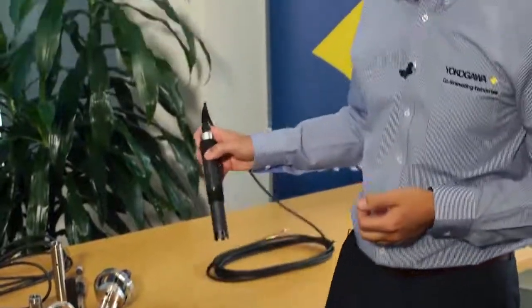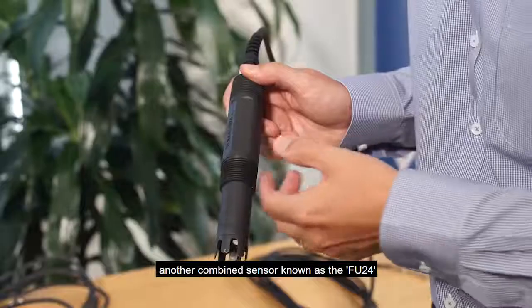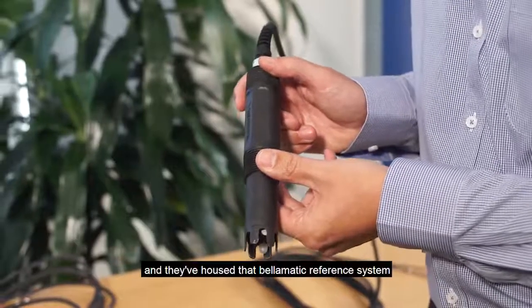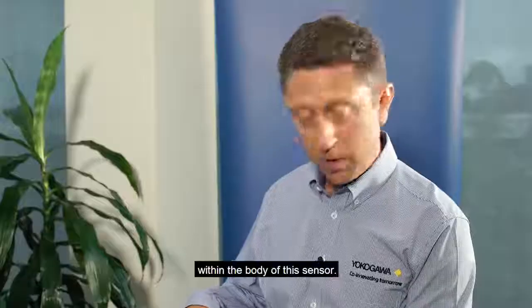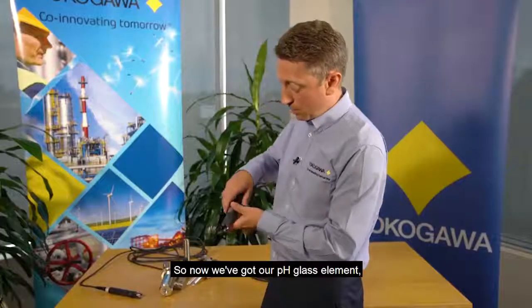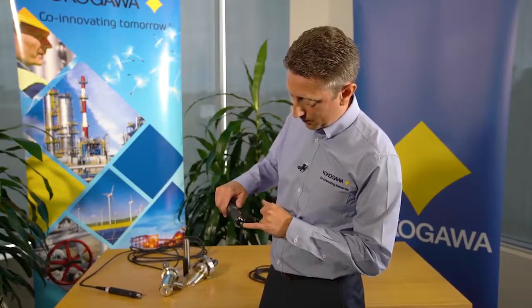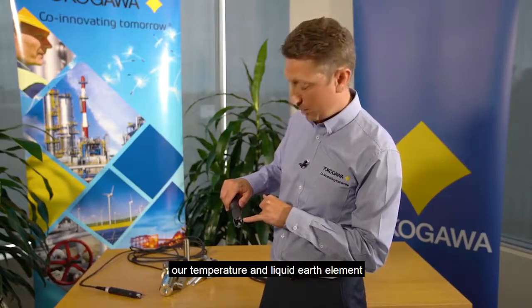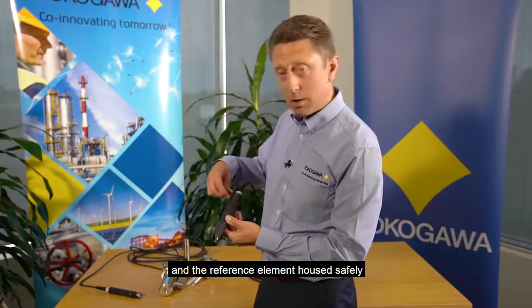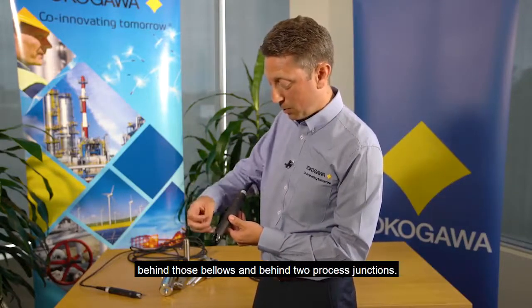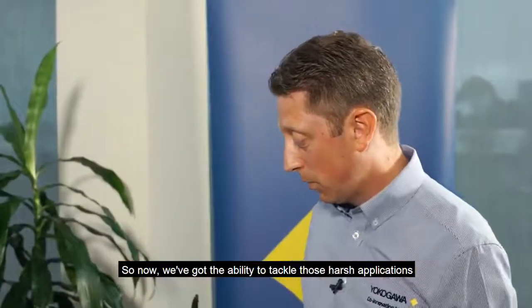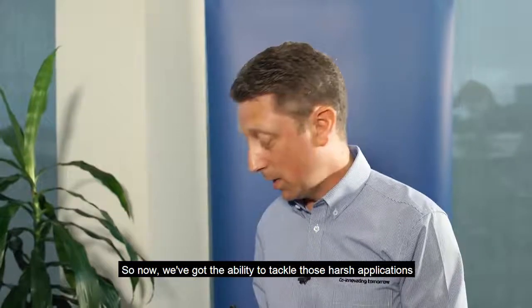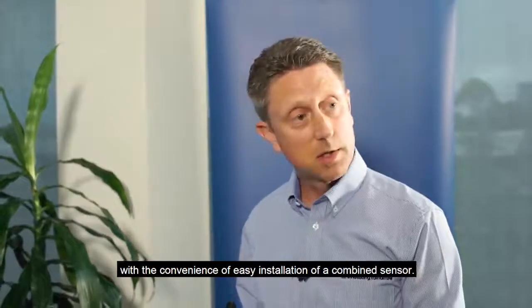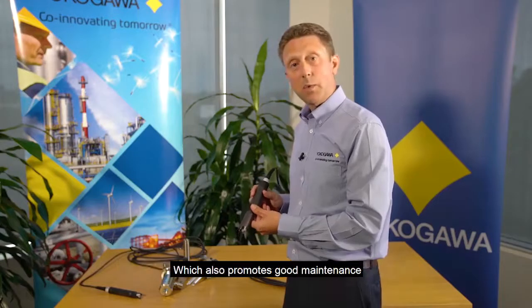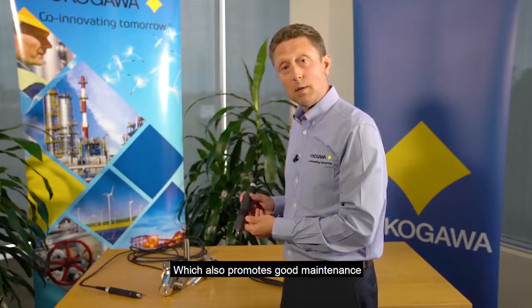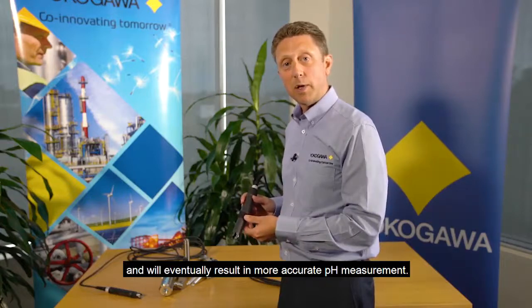Yokogawa has developed another combined sensor known as the FU24, housing that bellows reference system within the body of this sensor. Now we've got our pH glass element, our temperature and liquid earth element, and the reference element housed safely behind those bellows and behind 2 process junctions. So now we have the ability to tackle harsh applications with the convenience of easy installation of a combined sensor, which also promotes good maintenance and will result in more accurate pH measurement.